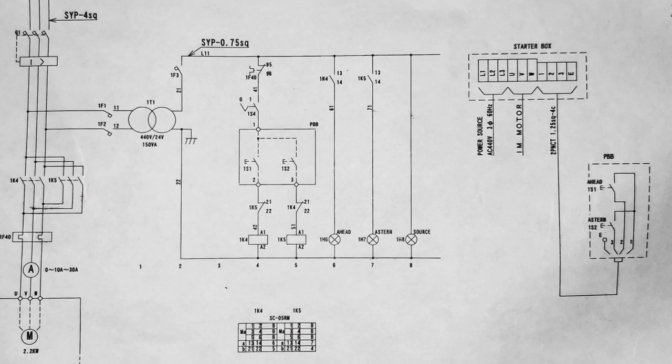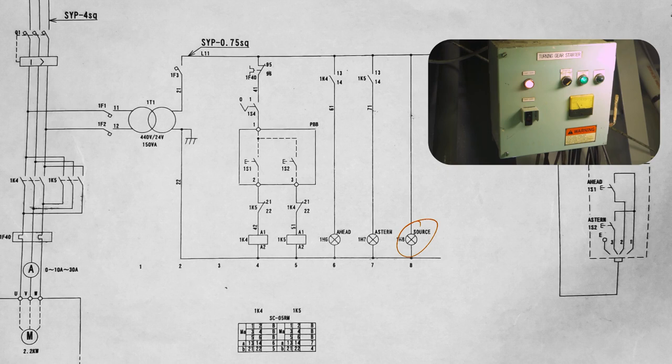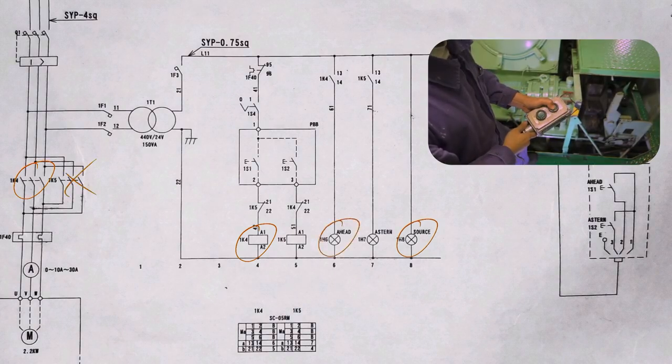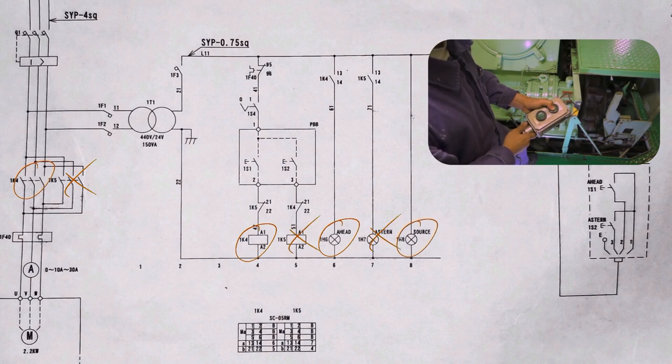Summing up from what I observed: panel has source voltage, motor forward rotation works as well as indicating light when forward push button is pressed. Motor astern rotation does not work as well as indicating light when astern push button is pressed.